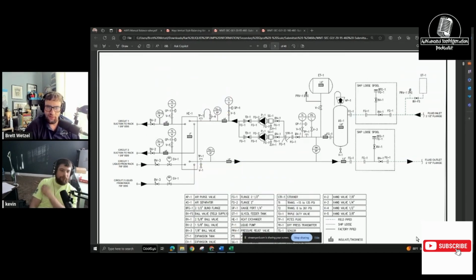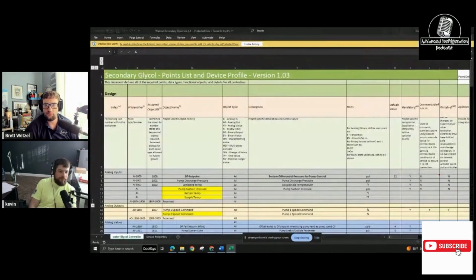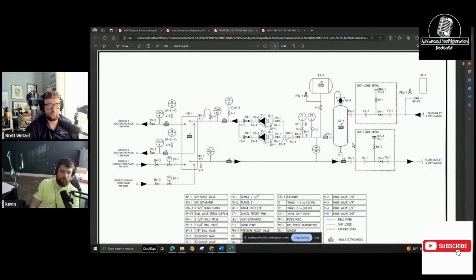Do you really? So we actually had a rack at a Walmart, and this thing would lose like 1.5 gallons of glycol and just make a mess. They had a bunch of leaking O-rings on unions. In order, the mechanical contractor that did it put the union on the wrong side of the ball valve. So in order to shut this thing down, you would have to drain down the whole store. So instead of running a service call out there every other day, we ended up putting one of those in, the autofill. This was everybody's idea. This thing worked flawlessly. That's horrible, though.